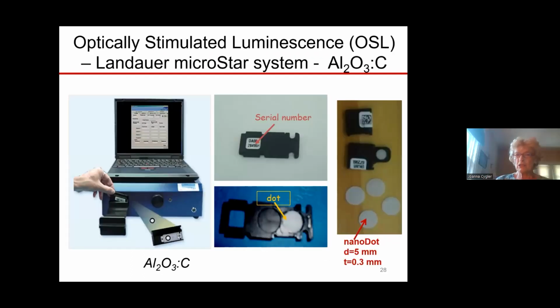Another luminescence-based detector is the optically stimulated luminescence detector, which has been relatively recently introduced into radiotherapy. It was used before in radiation protection. Here we have the MicroStar system, and it uses the detectors called nanodots, which are small discs made of aluminum oxide doped with carbon crystal. One could further miniaturize the already small nanodot detector, so they could possibly fit in natural body cavities, such as, for example, rectum, to measure the dose.